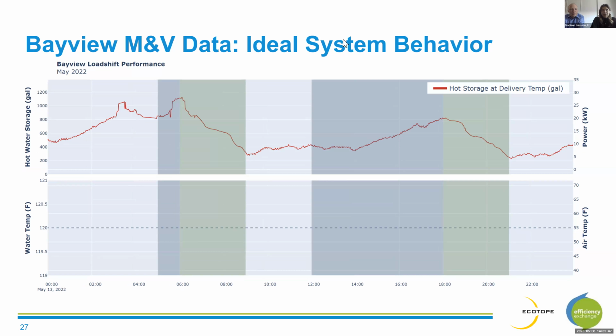Our storage tanks are around 850 gallons, but we're storing the water around 150 degrees and then mixing that with cooler water to supply it to the building at 120 degrees. So we're actually able to store around 1,200 gallons of hot water in those storage tanks.